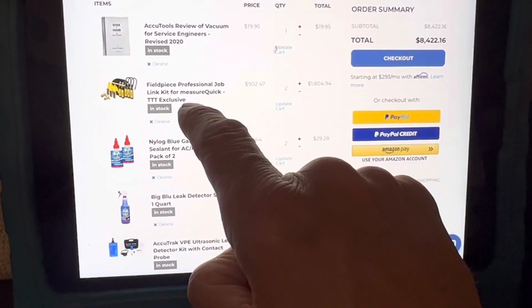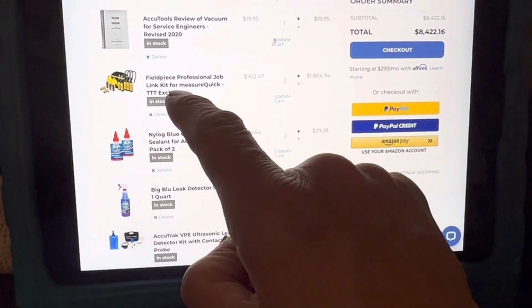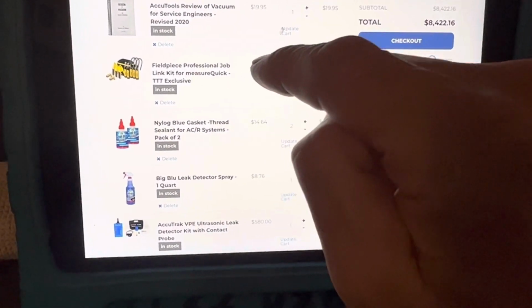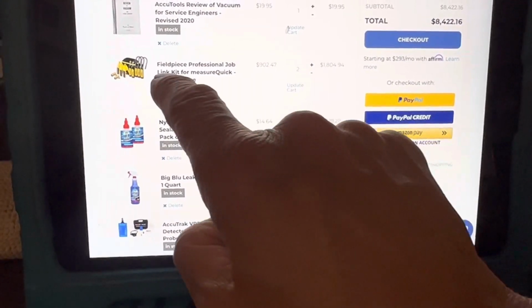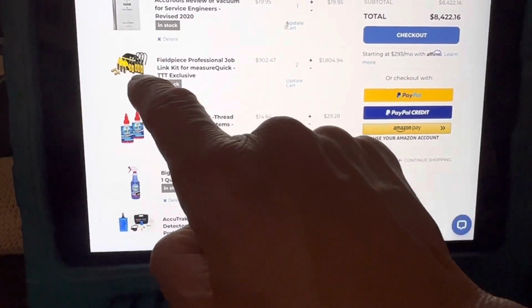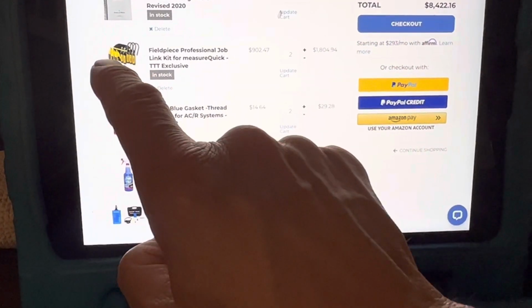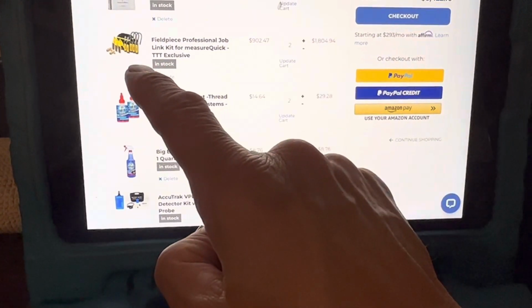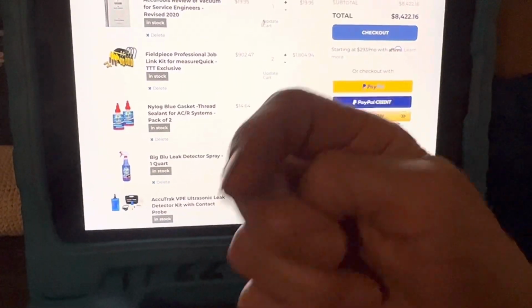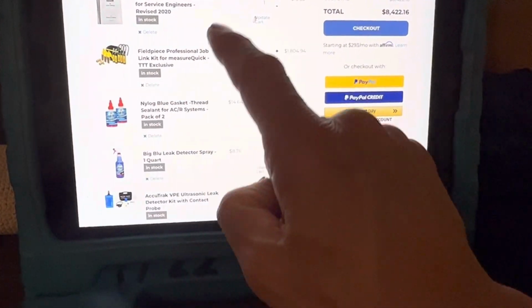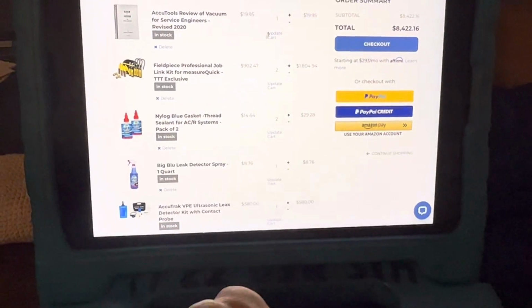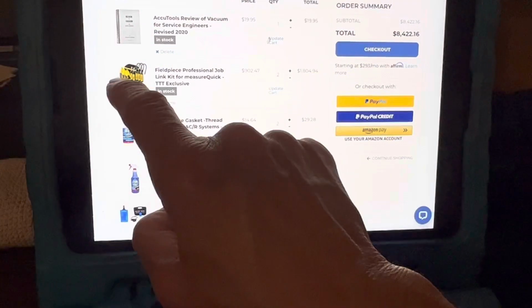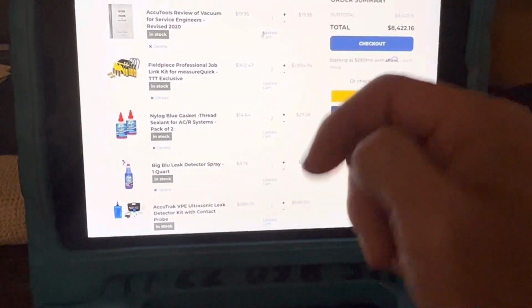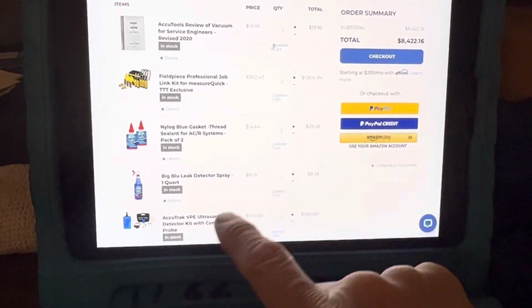The wireless sensor kit that you see me use from Fieldpiece, with the software I can download onto my phone or my pad — this is the kit right here. That's $902. You get 3 temperature probes, the pressure transducers, and 3 temperature clamps for refrigerant. You'll need that for superheat and subcooling, and you use it for when you have 2 evaporators and want to know there's cold refrigerant coming back to the compressor from the rear evaporator. You put one of those clamps on the metal hose coming from the rear of the vehicle — that's why you want 3. The other goes on the liquid line, and the other on the suction line coming from the evaporator. So that's the kit right there.